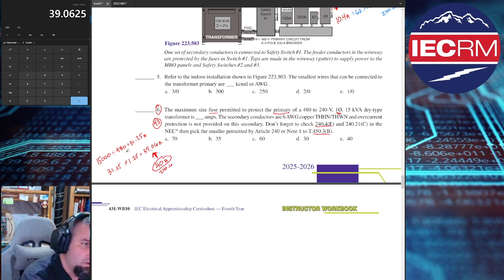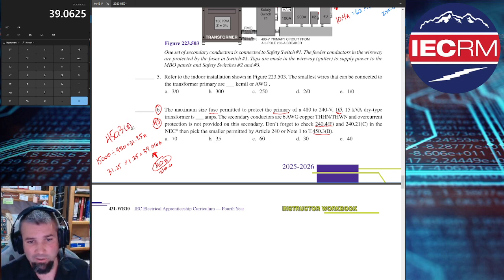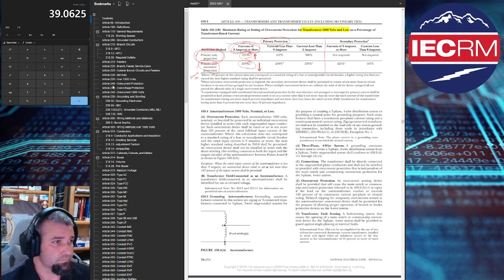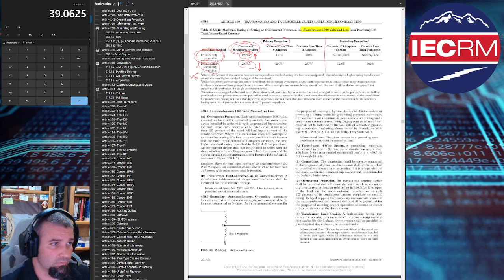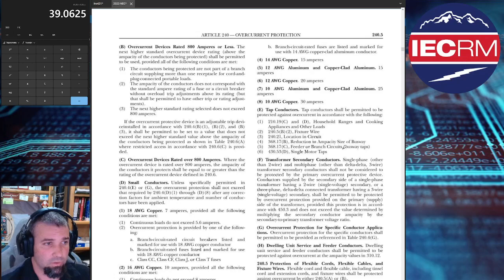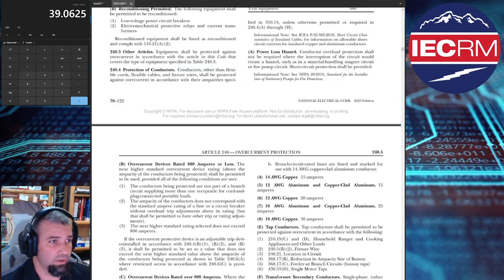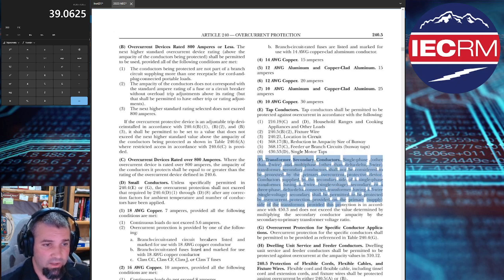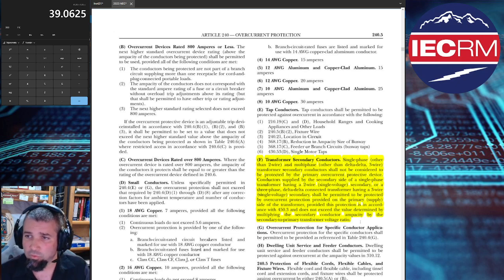Okay, so that's my number based on 450.3B. But now we gotta check 240.4 because there's always got to be somebody that's the party killer, right? They're the mood killer, and that mood killer is going to be 240.4. So let's go take a spin over and see what that says. Here we go. You're gonna love or hate this. Probably hate, and that's okay. Transformer secondary conductors, 240.4 is your protection of conductors. Okay, remember that one? We've done some work inside of there before. And 240.4F, it leads you right to in the question itself. This is the one we're going to be talking about. It's kind of a lot of words, but we'll break it down as best we can.